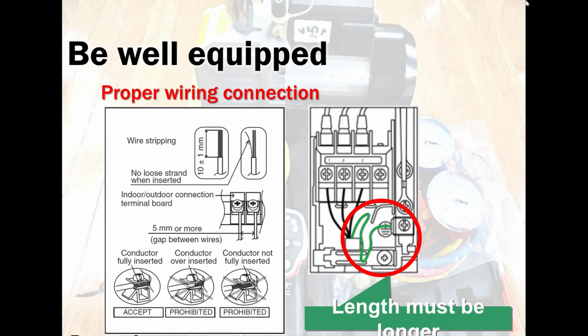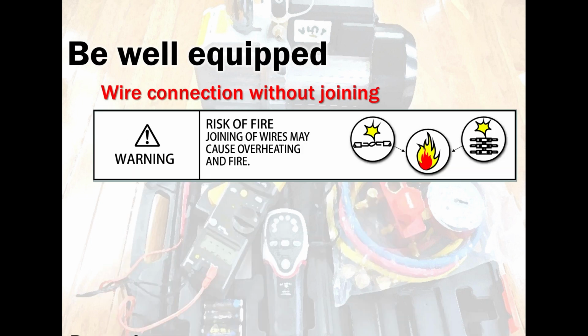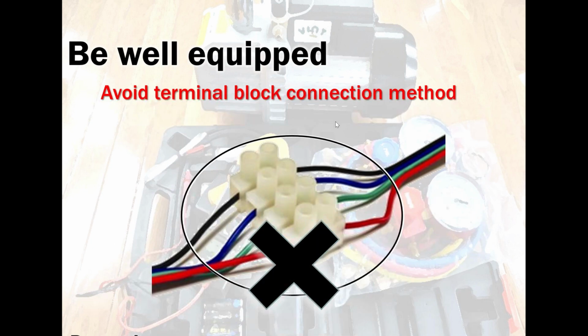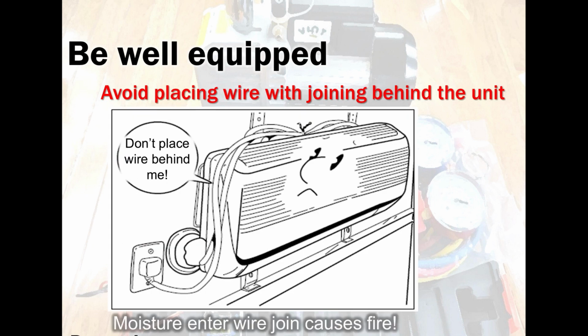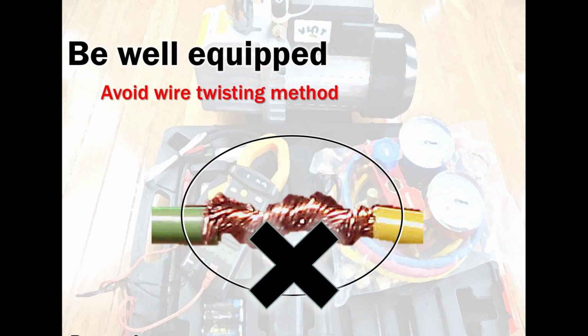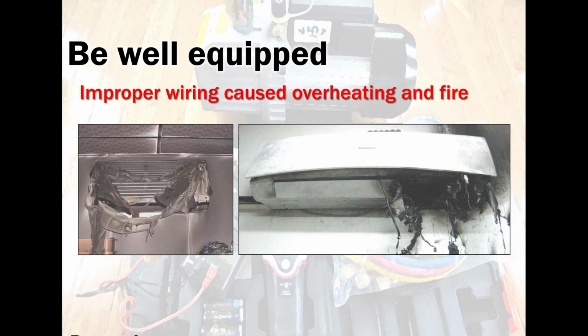And when the system shuts down, you can get away by resetting, but I'll tell you, after a week or so, you'll be called again. So always remember not to cut wires, not to join wires. Never use connectors. Never use connectors, never use Marettes, never join wires, period. No matter which brand you're working with. This is free advice. Twisting wires, not acceptable. Please do not join wires. Get a control cable that is complete from end to end.